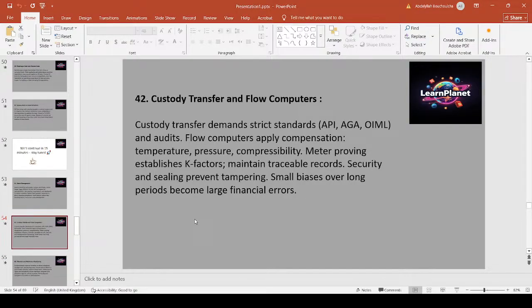Custody transfer demands strict standards: API, AGA, OIML, and audits. Flow computers apply compensation for temperature, pressure, and compressibility. Meter proving establishes K factors. Maintain traceable records. Security and sealing prevent tampering. Small biases over long periods become large financial errors.